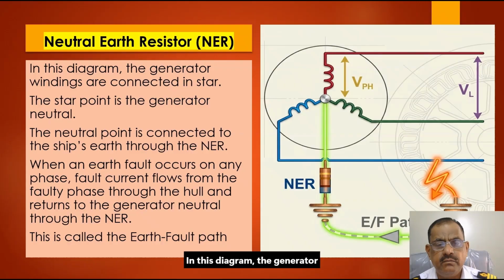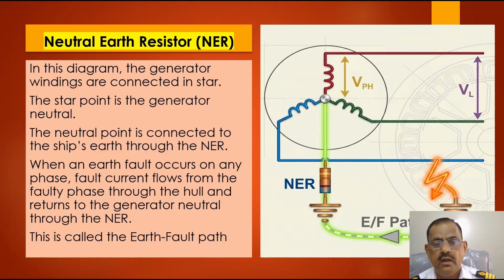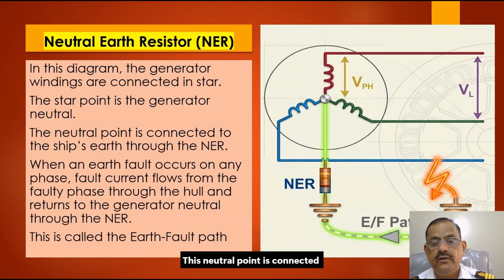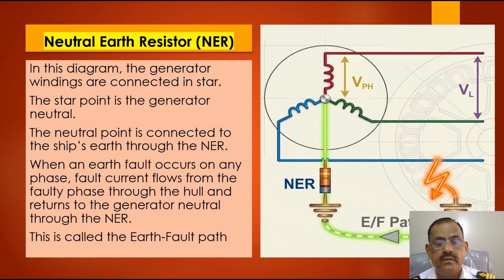In this diagram, the generator windings are connected in star. The center point of the star connection is the generator neutral. This neutral point is connected to the ship's hull through the NER. Normally, earth fault current flows through the NER.